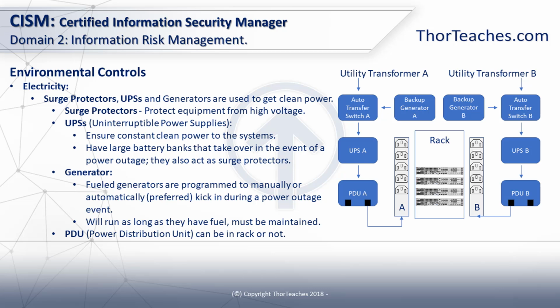The power is then sent to the PDU, which is a power distribution unit. They can either be big units the size of a couple of racks, or they can be housed in the rack itself. And that's then attached to the electrical outlets that are in the rack, which all the servers are plugged into. Exactly the same flow on transformer B, and then each server in that rack would have one power supply plugged into A and one power supply plugged into B. So if anything broke in the A chain or the B chain, it will still have full power because the servers are designed to a spec where they can run on just one power supply.